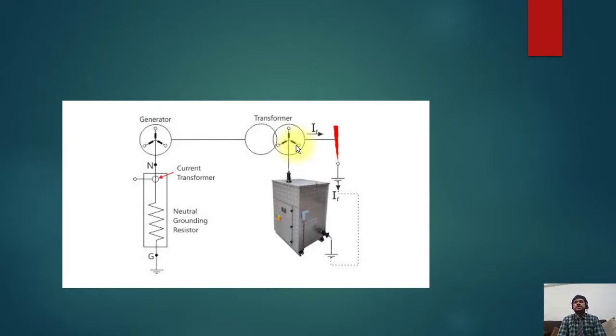The need arises for this NGR as it provides a cost-effective solution. For example, if your equipment is designed at 10 KA short circuit level and the short circuit level is now increased up to 20 KA, if fault occurs on that transformer, the transformer can easily be damaged because the fault level has increased. So how can we use the same equipment?